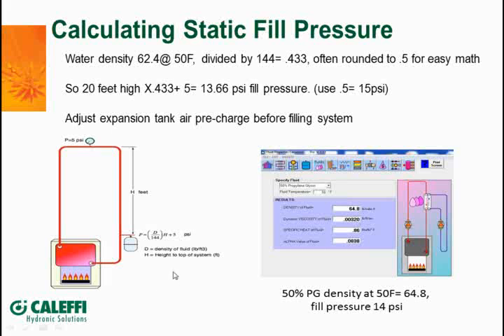So here's the formula for figuring out what your static fill pressure needs to be. Let's say we've got a 2-story house, so from the bottom in the basement here where the expansion tank is mounted to the uppermost point in the system, let's say it's a hydronic system with a baseboard up there, we've got about 20 feet.